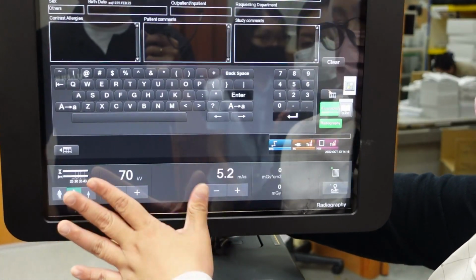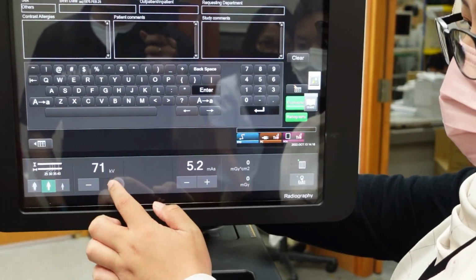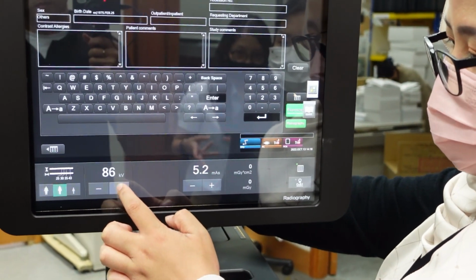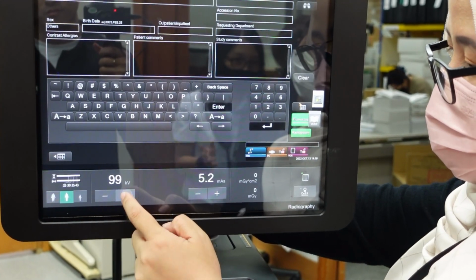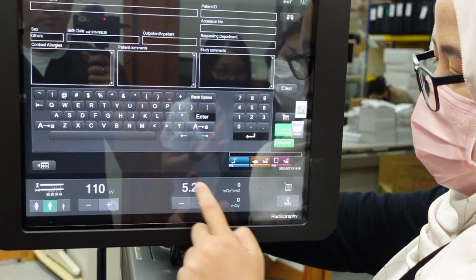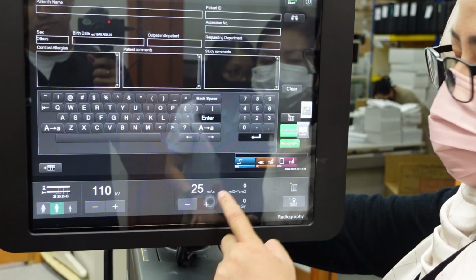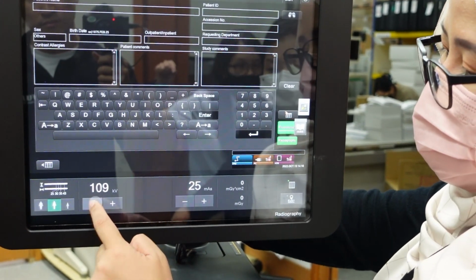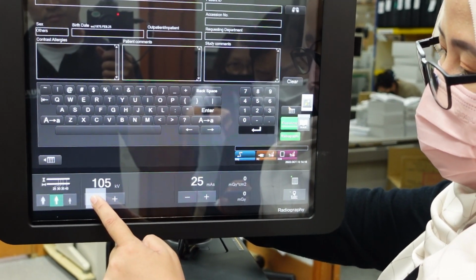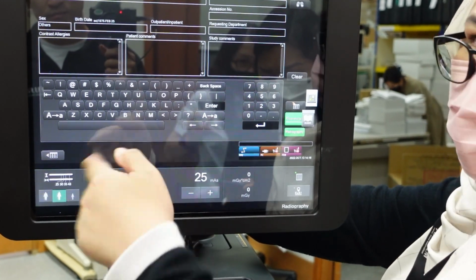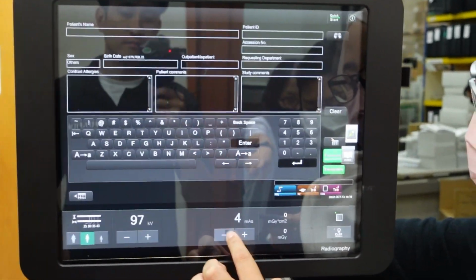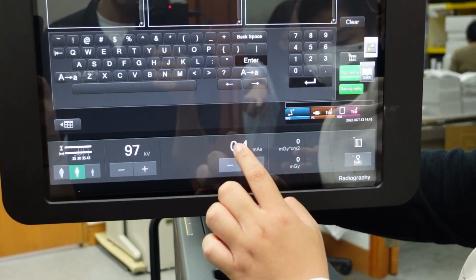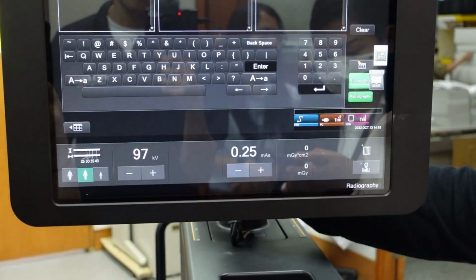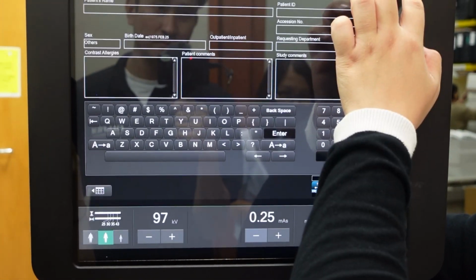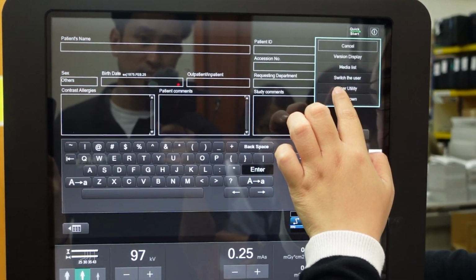Okay. Maximum kV 110 for static radiography. mAs 25. 25. Okay. Minimum kV is 40. 40 and 0.25. Yes, this one 0.25. Okay. Right.